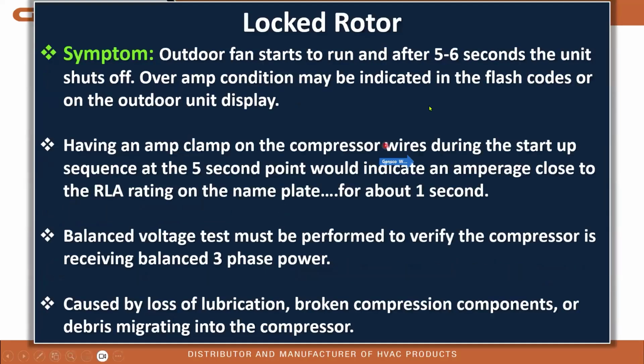The symptom of a locked rotor compressor would be that you walk up to the unit, you have the unit on to run, the unit starts to run, the outdoor fan comes on, and after about 5 or 6 seconds, the unit shuts off. It's the most common symptom of a locked rotor compressor. You may have an overamp condition indicated in the flash codes on the unit or on the unit display or even on the thermostat, or even the indoor head if it's a wall head flashing an error code. You look up the actual error code and find out it's an overamp condition due to the locked rotor.